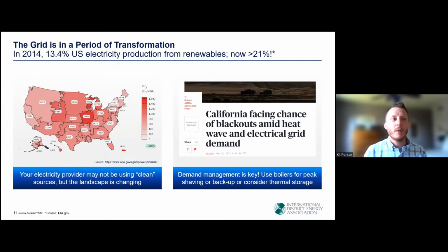So it's important to do an upstream carbon emissions analysis and remember that over time, the grid will become cleaner as more renewables come online through investments made by the governments or utility providers. So even if your power supply is not green today, consider the fact that since 2014, renewables used for power generation in the US has increased substantially, and that's not slowing down. But with all this being said, there's not an unlimited supply of electricity available, and that's why it's important to digitize your building and manage electrical demand, as well as have contingency plans in place for being able to continue to operate your building's heating and cooling systems. So contingency plans, they may include having a phased-in approach to full electrification as the grid becomes cleaner and more stable, using backup boilers, and/or using thermal storage as part of your design to do some peak load shaping.